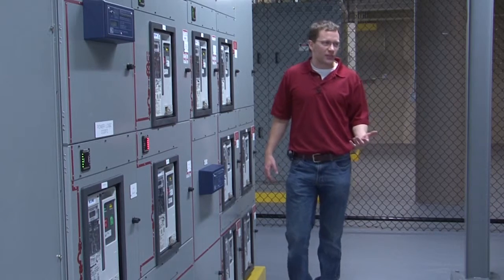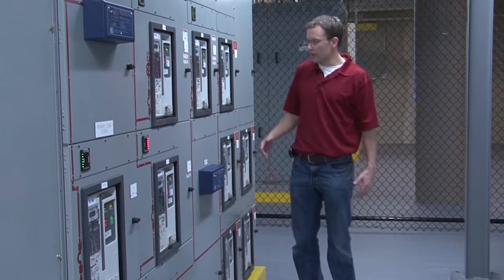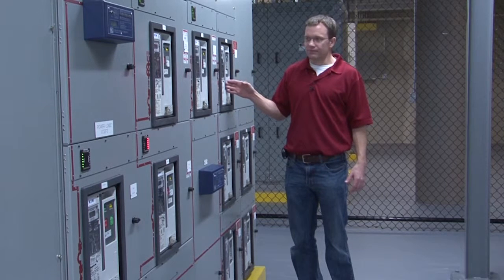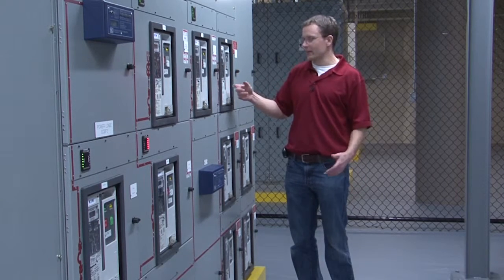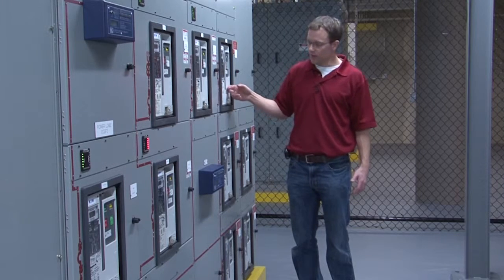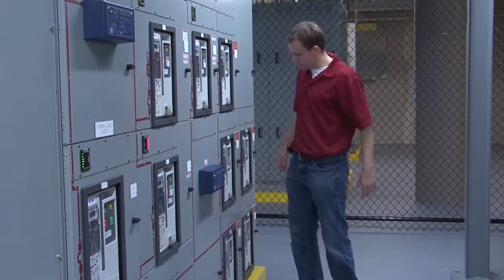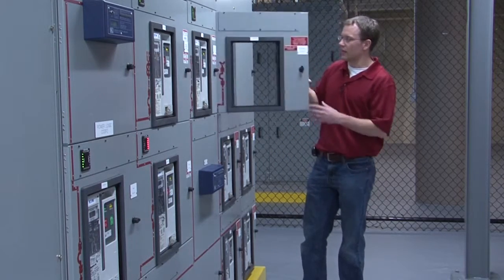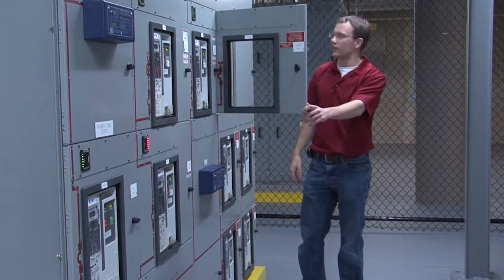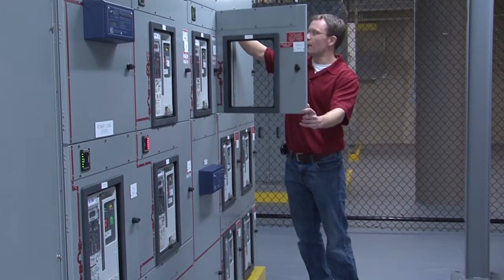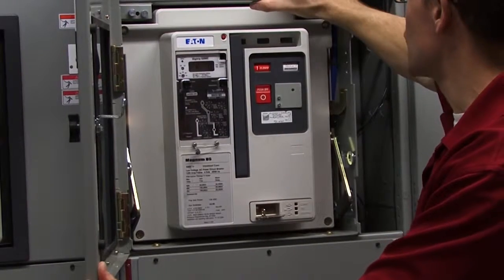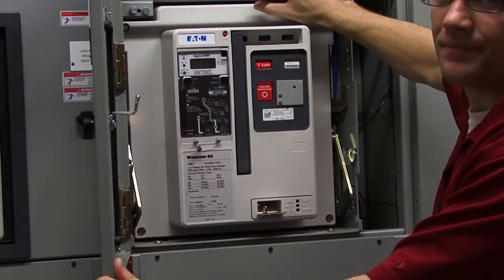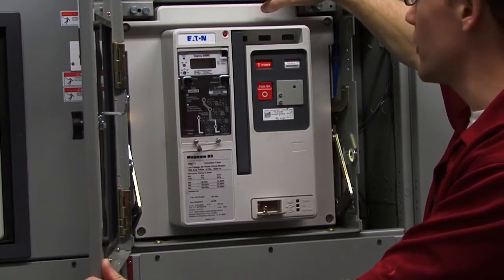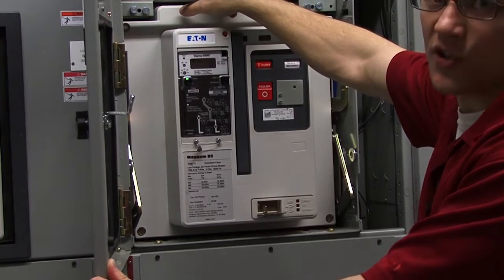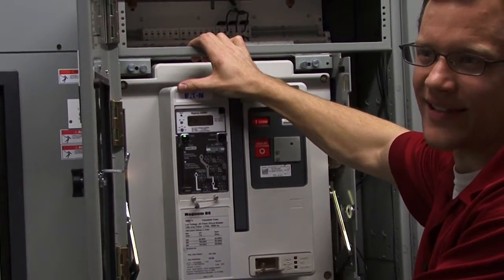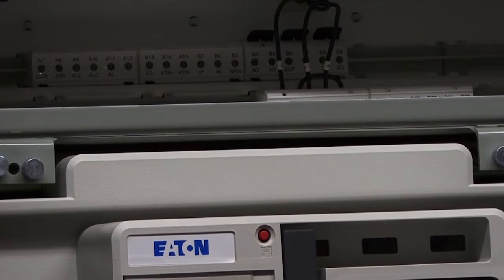The UPS modules themselves can protect in a faulted condition, so if there were to be a ground fault, the UPS should limit its own damage automatically and without the aid of a breaker tripping. So these 5 breakers have had that feature disabled, and there is a jumper from B6 to B7, and that's the jumper that disables ground fault. This jumper here disables zone interlocking, and this jumper here just jumps across what would normally be an input for a ground sensing CT, which is not present on this board.